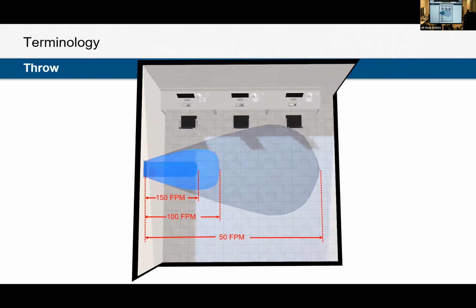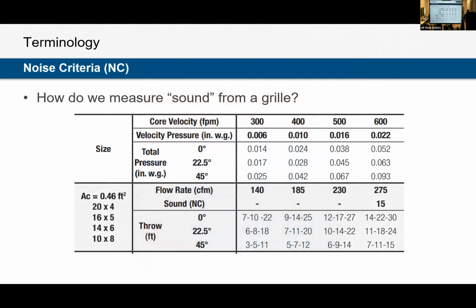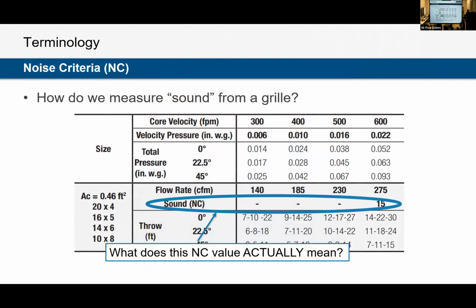150, perfect. So your throw is the distance air will travel out of the air outlet. And usually we're cataloging at these specific velocities. We're looking at what distance does our air achieve 150, 100, and 50 feet per minute. If you remember from our mixed air video, we are always trying to target 50 feet per minute in the occupied zone. That is our goal. So that is throw. We'll talk more about throw towards the end, but again, just terminology here.